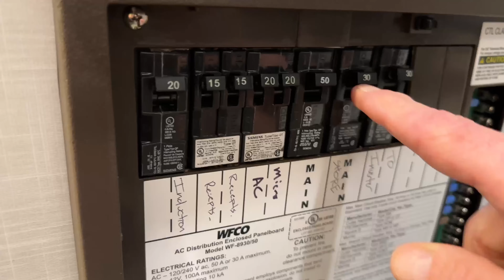There's no automatic transfer switch, so in this case, you are the transfer switch. It's a good idea to go inside your RV, flip the main breaker off, then connect the power cord, then start the generator. Starting them is usually some kind of lawnmower kind of action. Once it's started and smoothed out and running, go inside and flip the main breaker back on, and you're good to go.